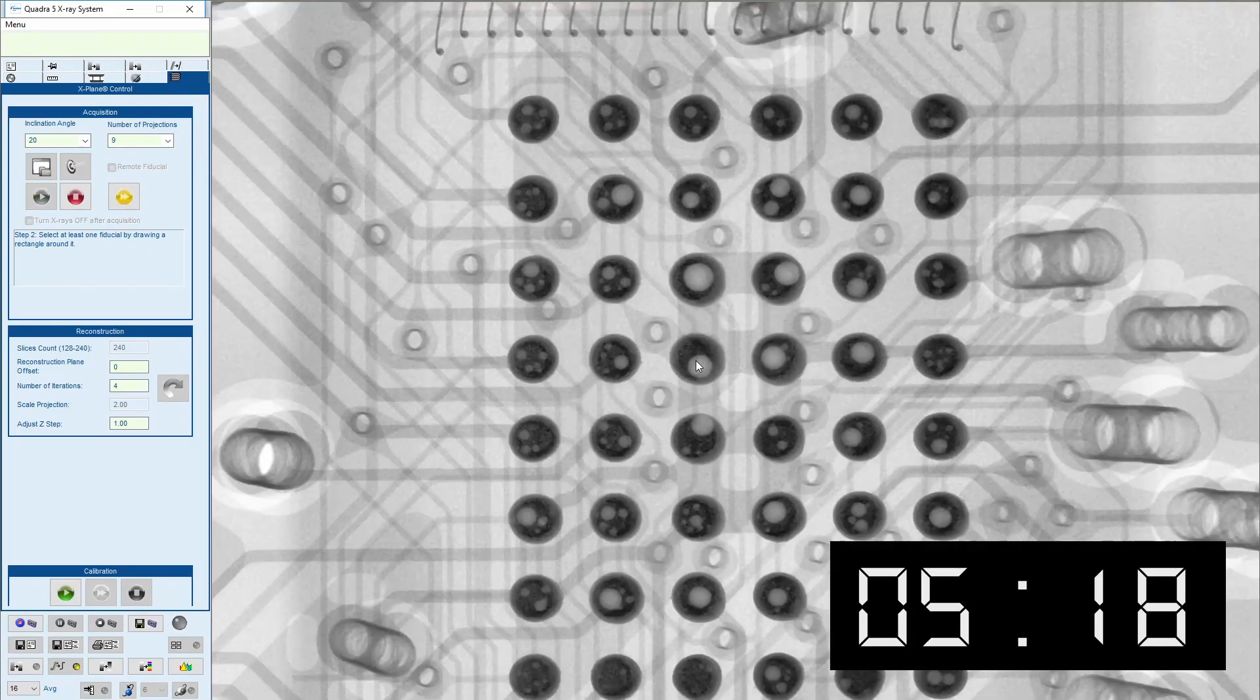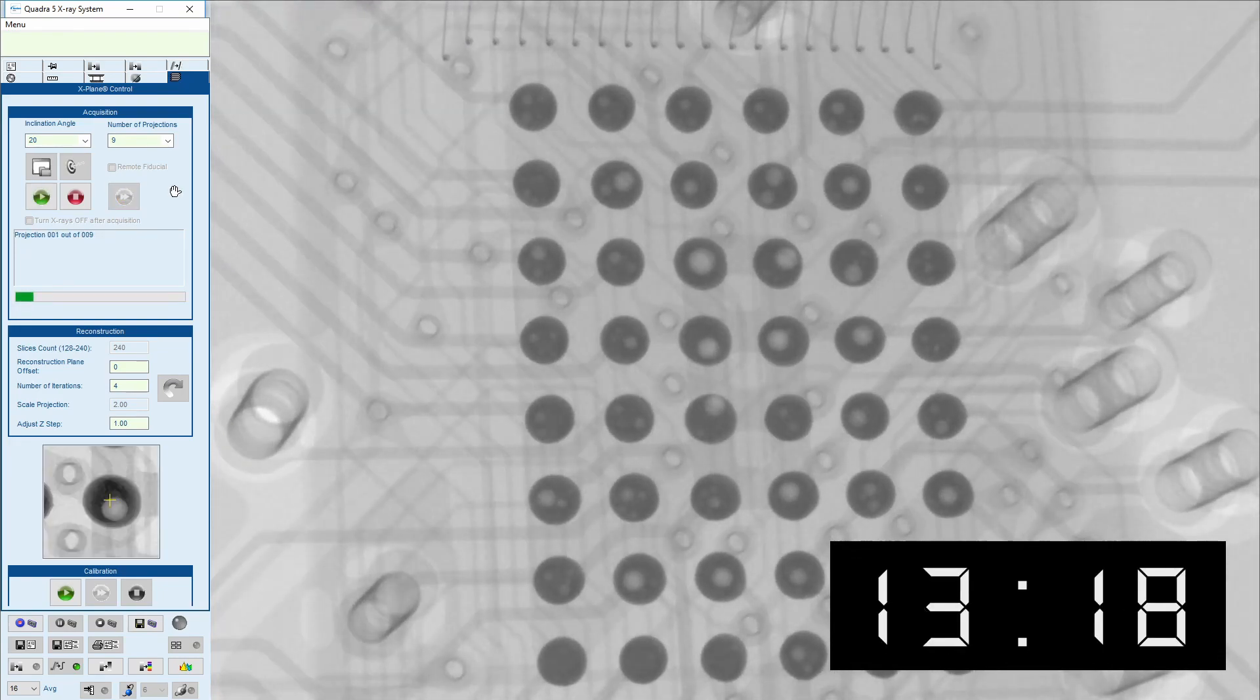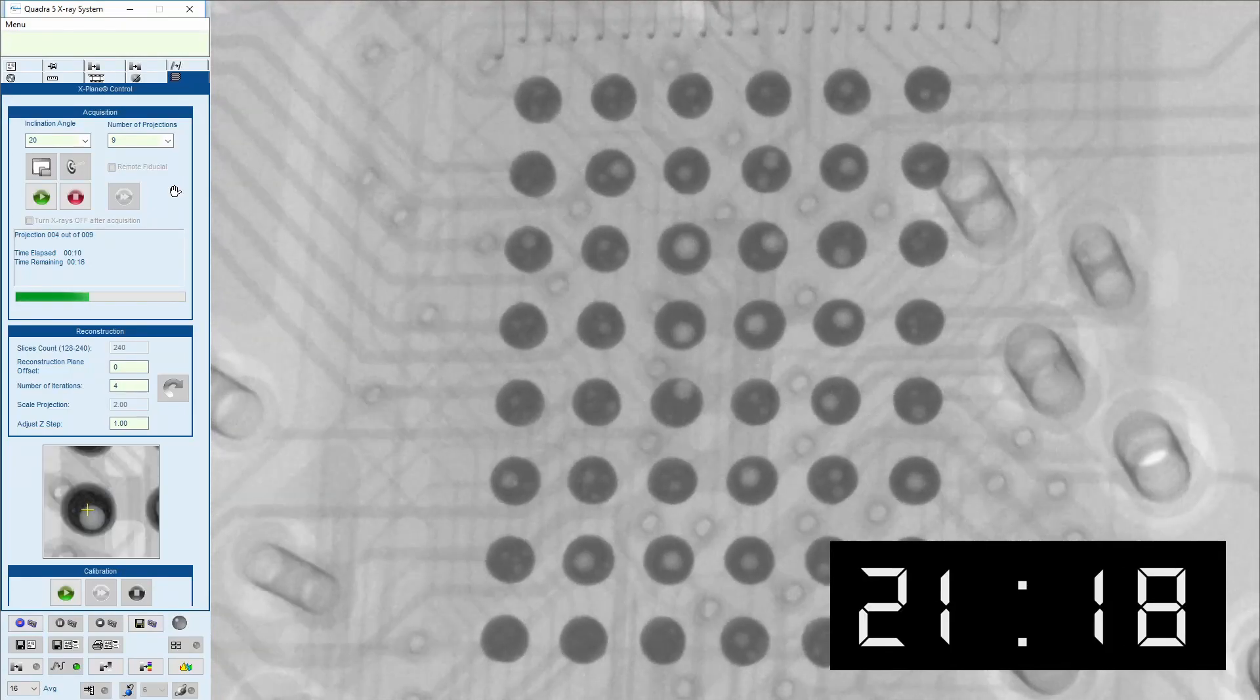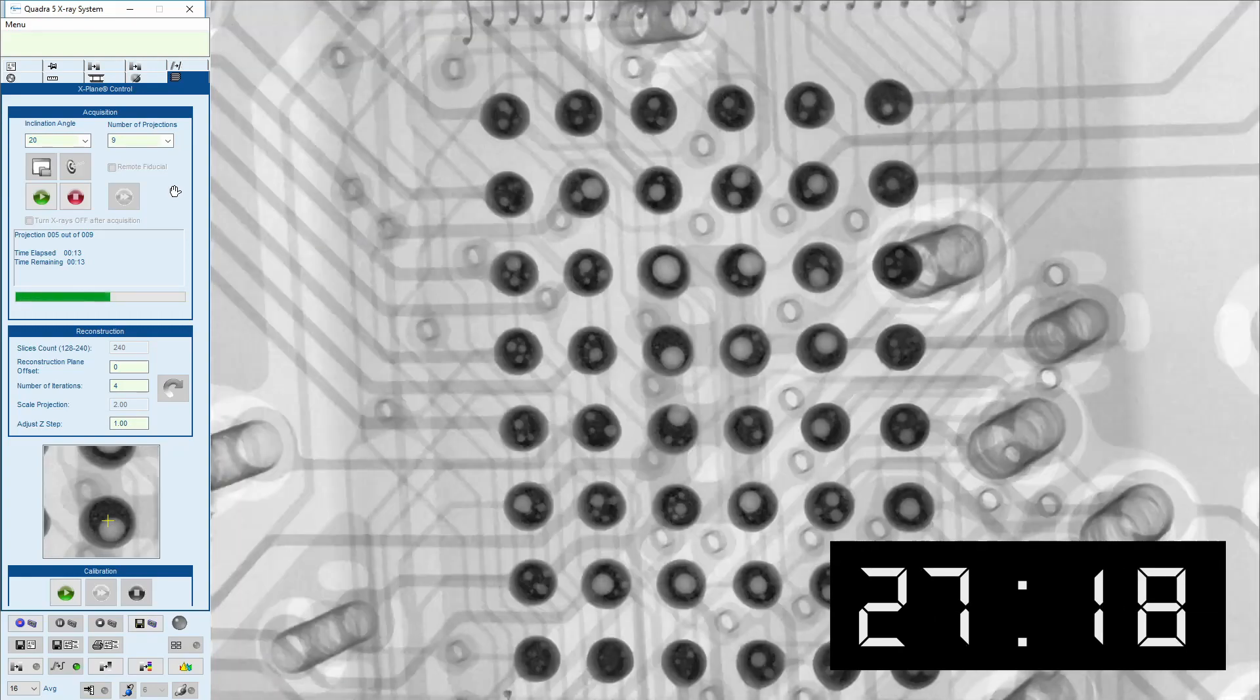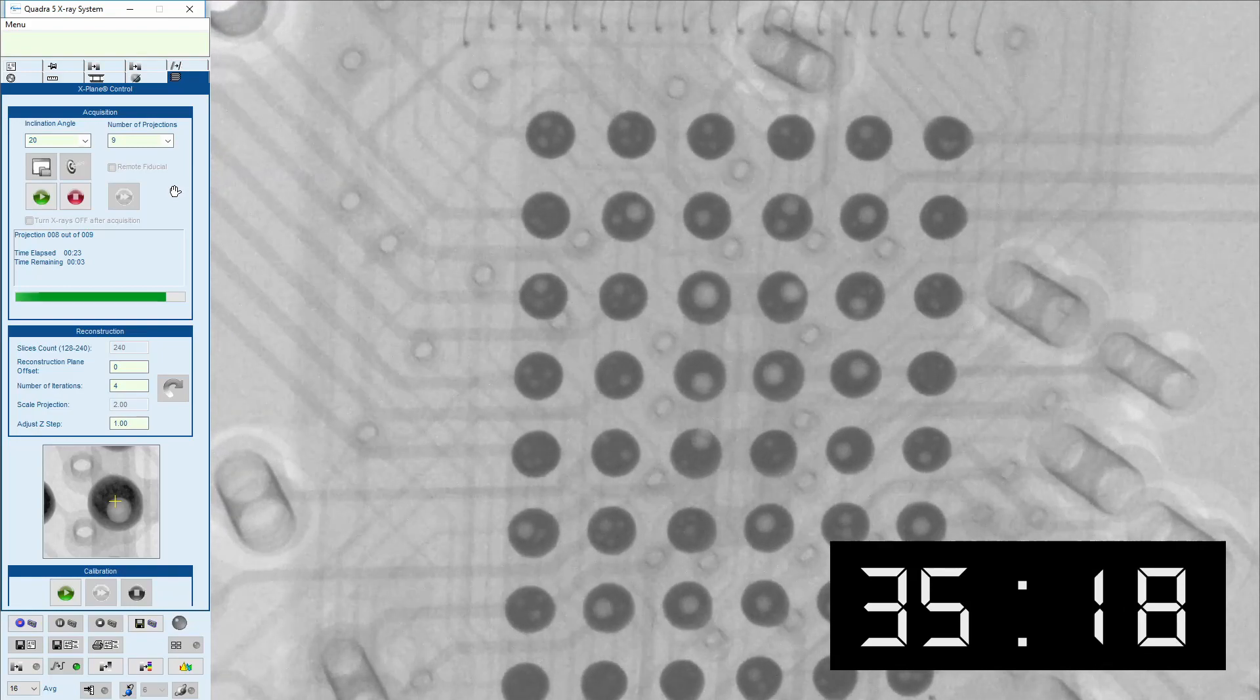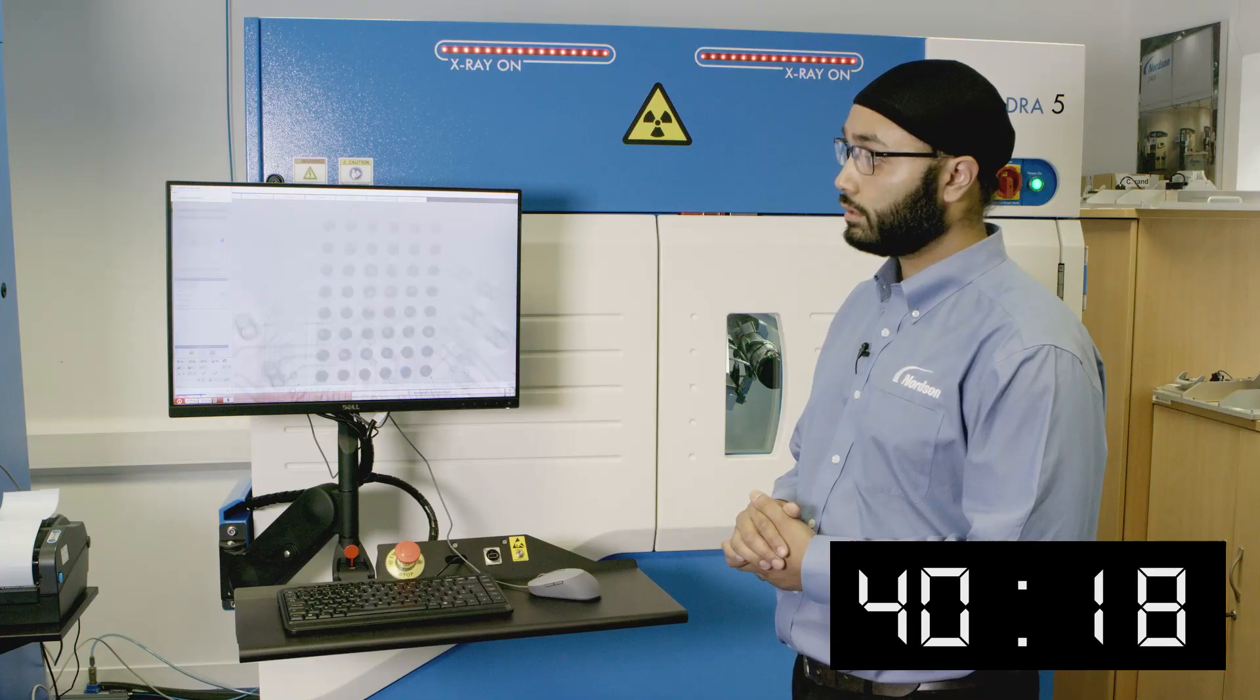Draw the fiducial. Click start scan. The software will take one image every 40 degrees. And as quick as that, the x-plane scan is finished.